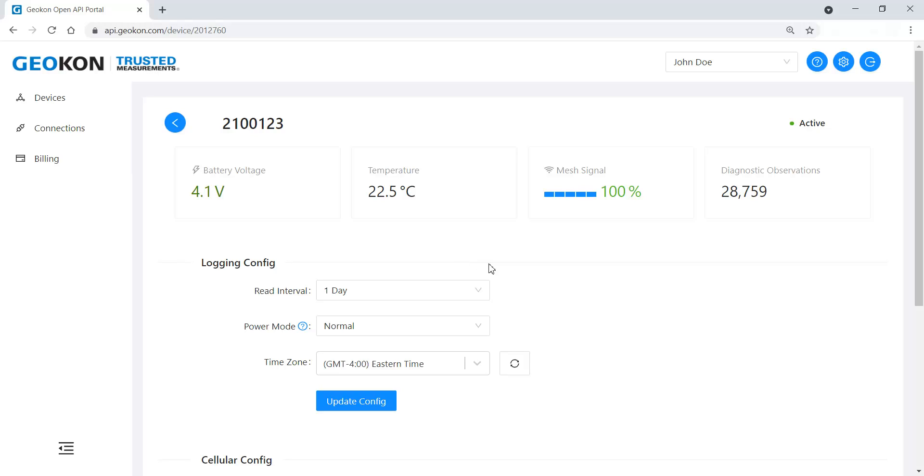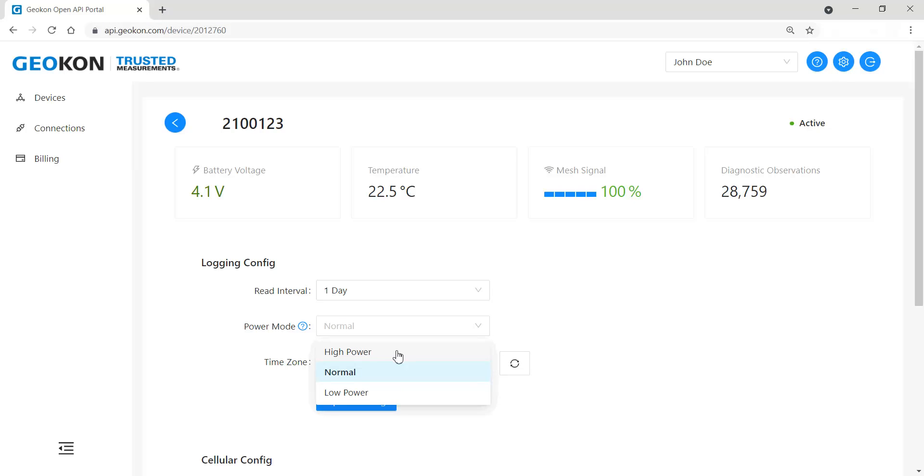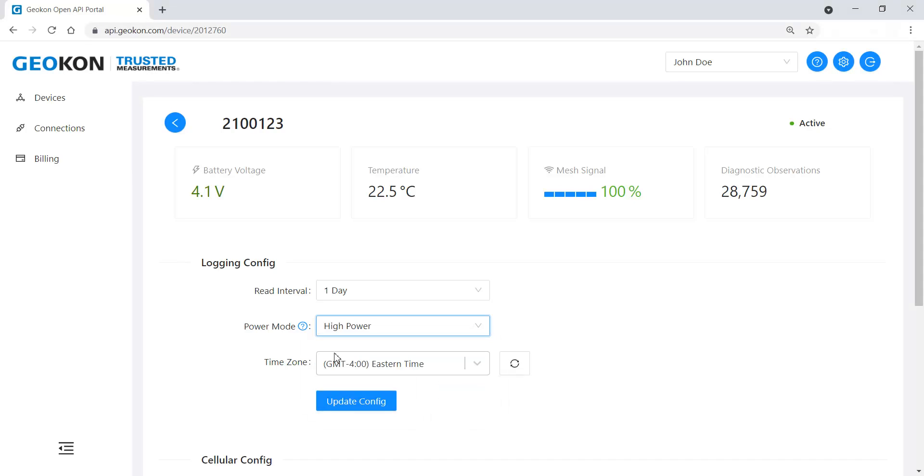The read interval controls how often the network takes a reading. There are three power mode settings. It is best to set the power level to high while commissioning the device. Check the time zone to make sure it is correct for the network location and change it if needed. Save any changes you have made by clicking the Update Configuration button.